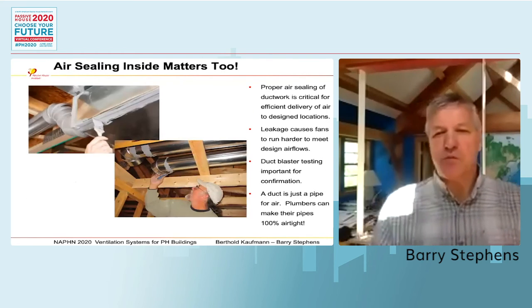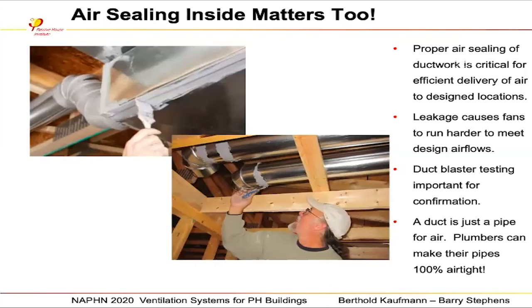The other thing that's really critical is air sealing. I say here, air sealing is just as important on the inside as it is on the outside. And sealing these ducts is really critical. It's something that you want to make sure does get done well, so you can deliver the air to the places you need to, in the amount you need.